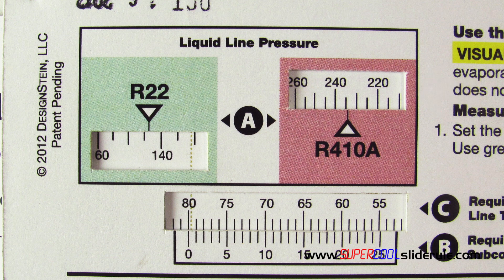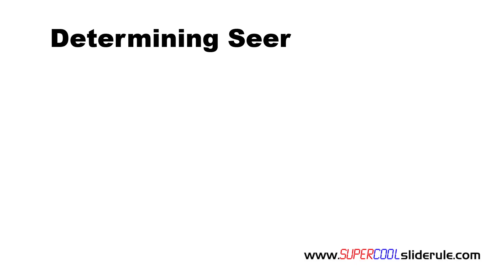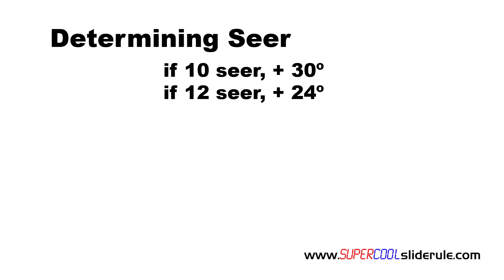Referencing a temperature pressure chart will give the same answers. Next, we are going to use an educated guess as to the efficiency of our equipment. If our equipment is 10 SEER, we will add 30 degrees to our ambient temperature. If it is 12 SEER, we are going to add 24 degrees. And if it is 14 SEER, we will add 20 degrees.